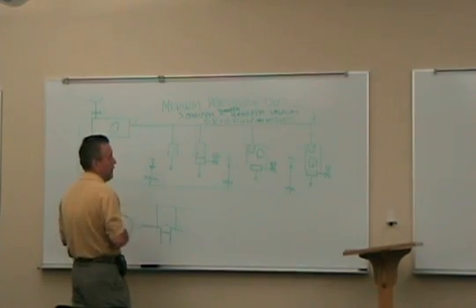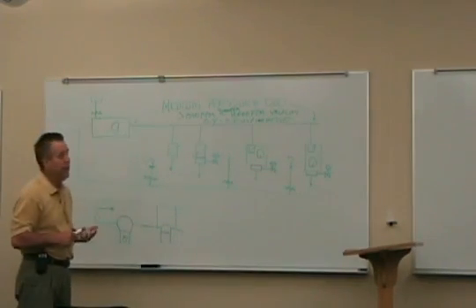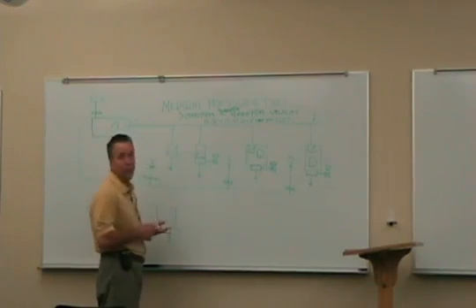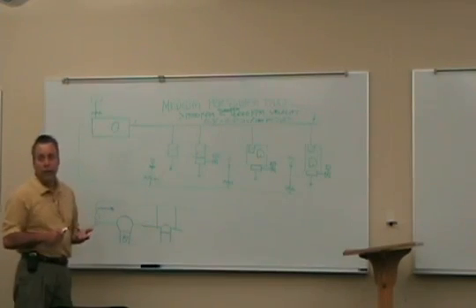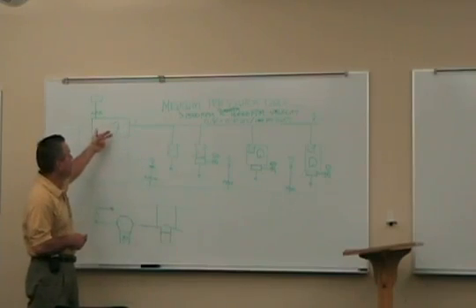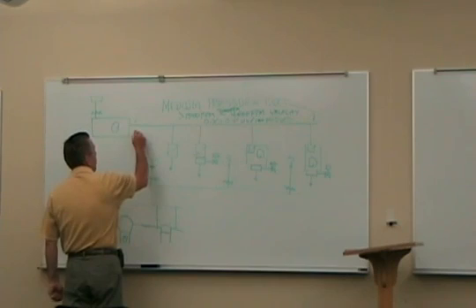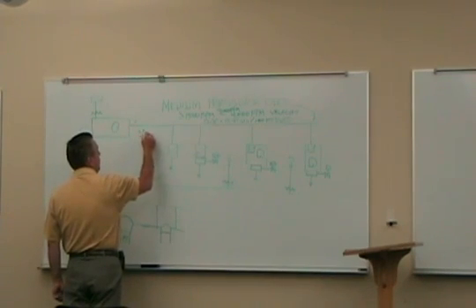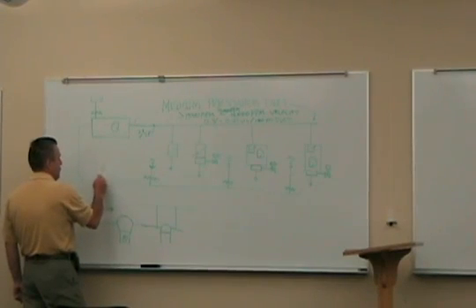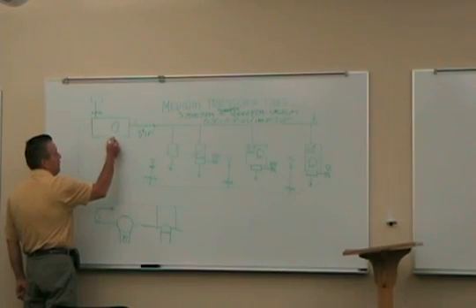And you have to be very careful with the fittings. It can be bought in spiral duct. It can be built. SMACNA, the sheet metal folks, have recommendations for fabricated duct. You look at your pressure that you want to build it to. For instance, the engineer calculated this, and he said that this classification is probably in the 3-inch range, 3 inches of static pressure. And this is probably 1 inch static pressure. You know, the air handling unit may be 6 inches.